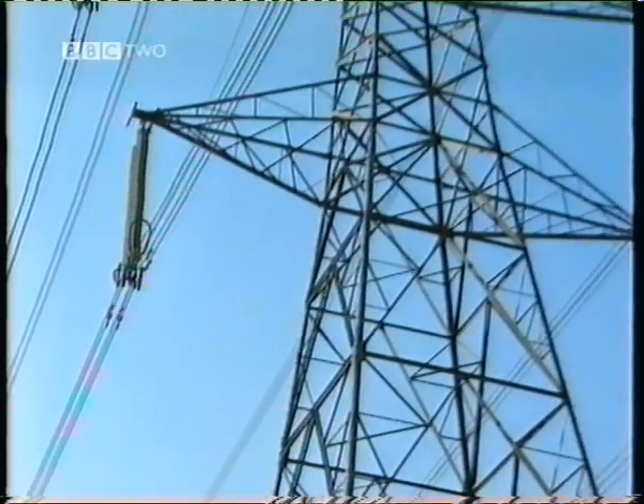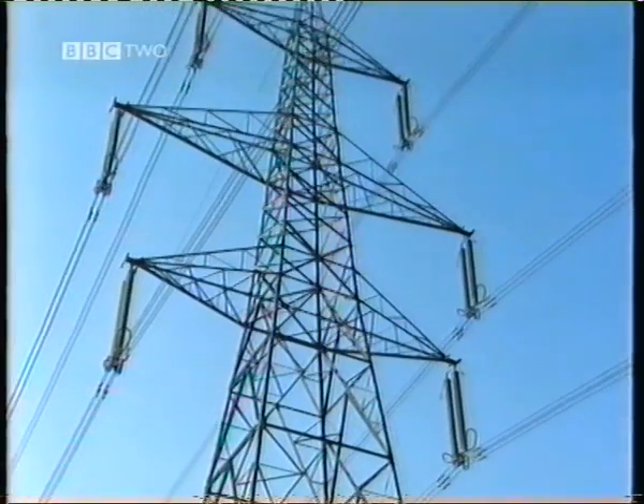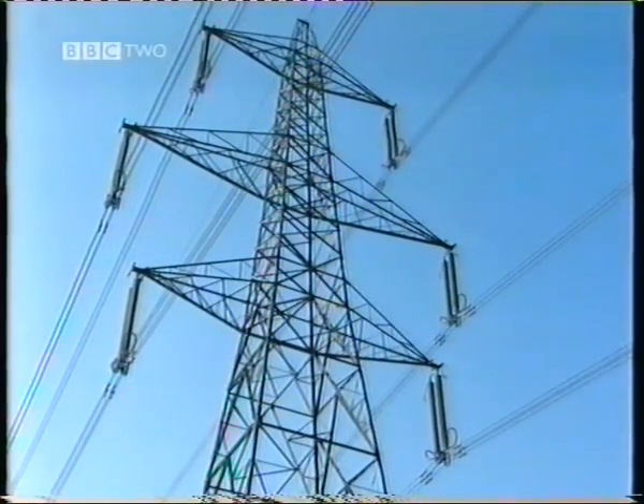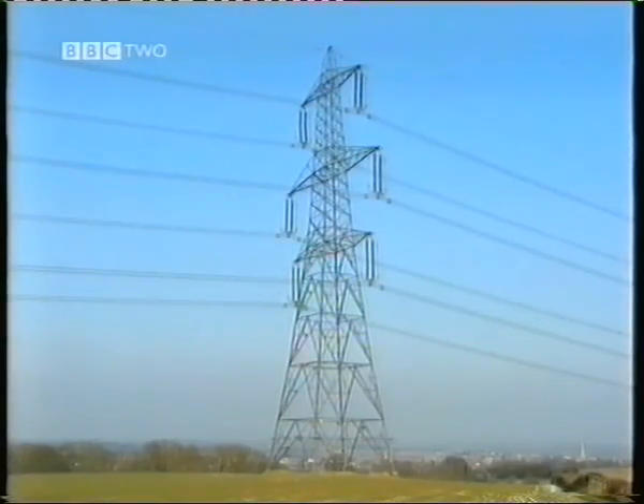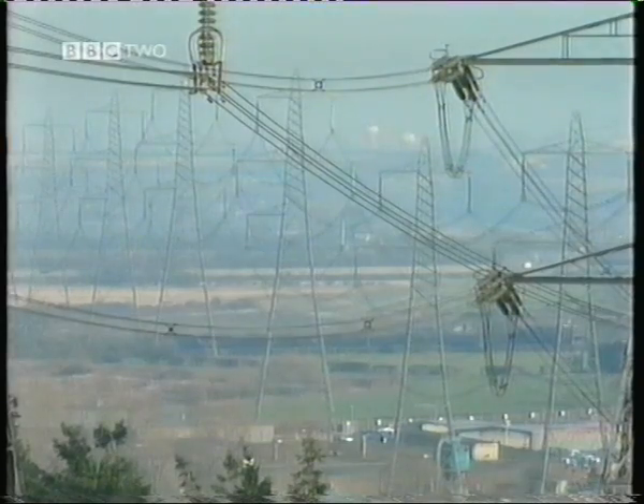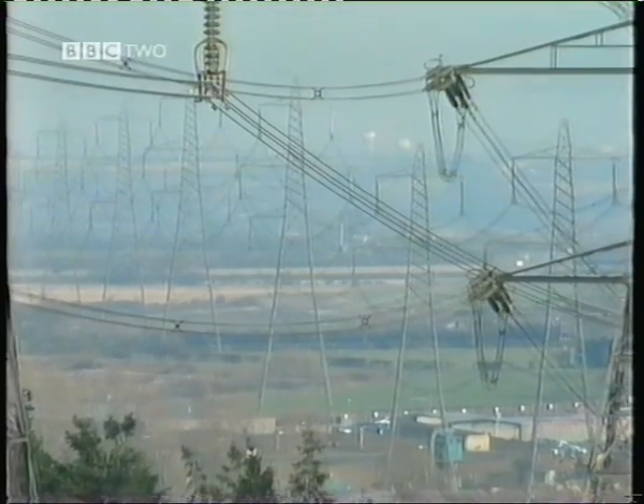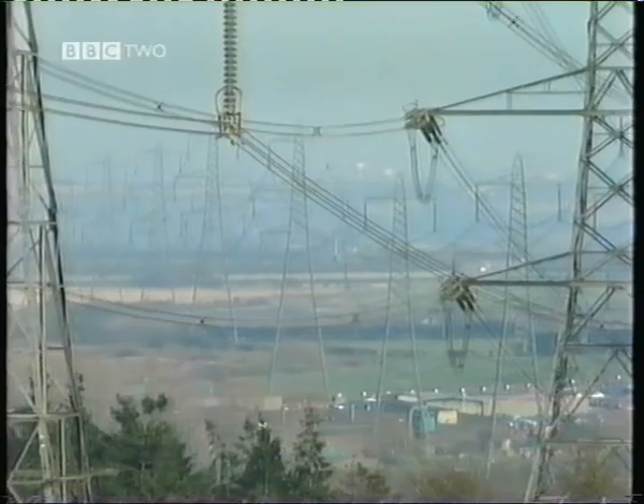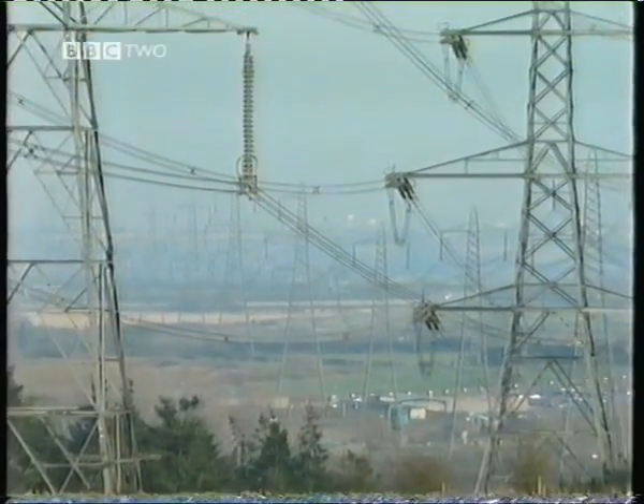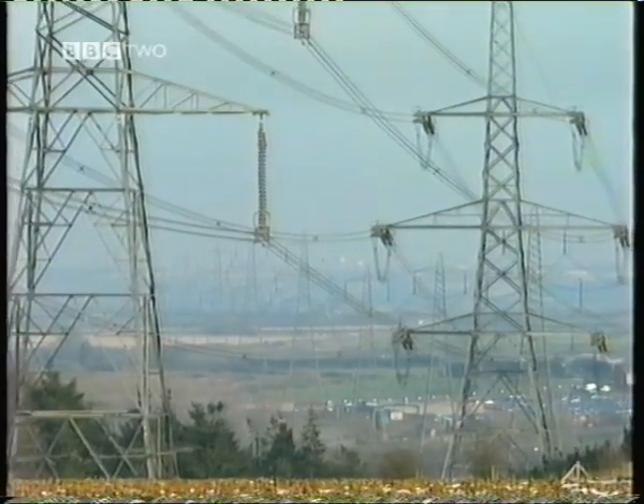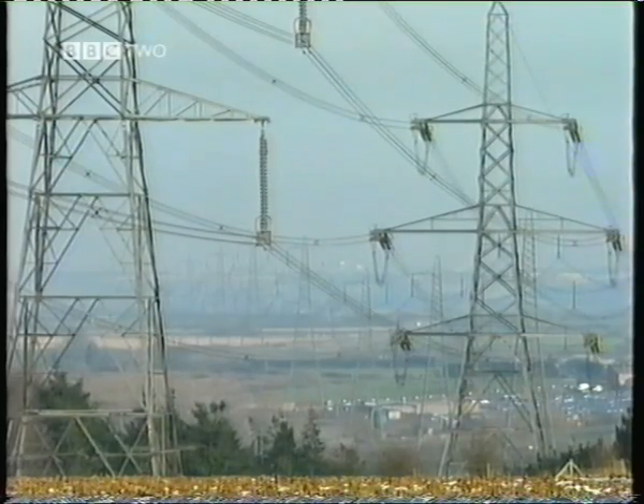Air ought to be a pretty good insulator. It's made up of molecules, small clusters of atoms, strongly bound together by electric charges, but overall neutral, and so not able to transport net charge. Apart from price, there's another advantage to air. At full load, lines get rather warm. A few tens of watts per metre of heat are carried off from the cables by the air. How much air do we need for the insulation of the supergrid at 400 kV?